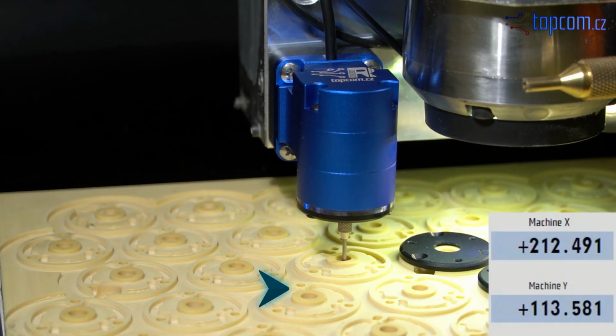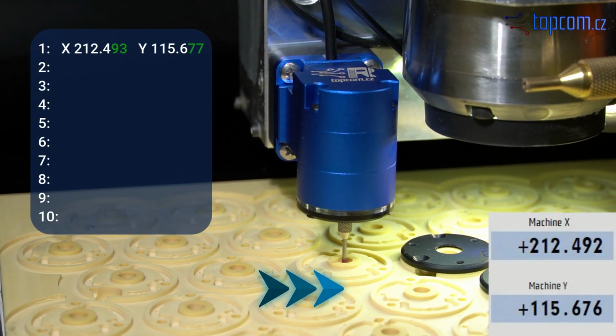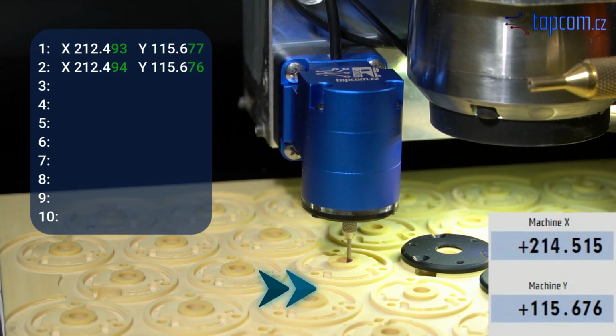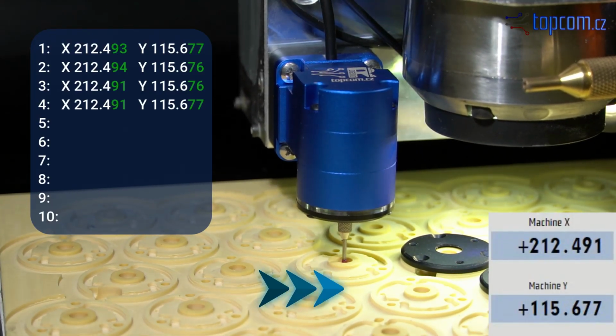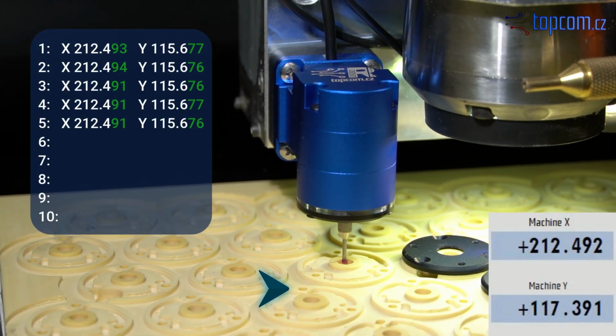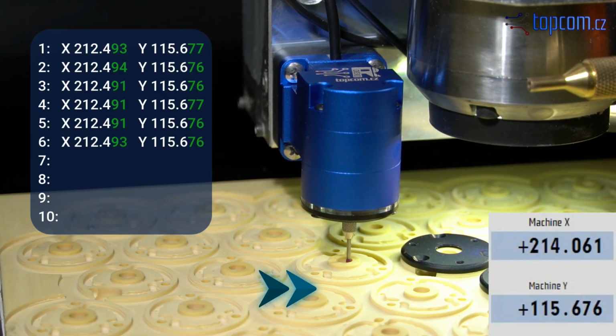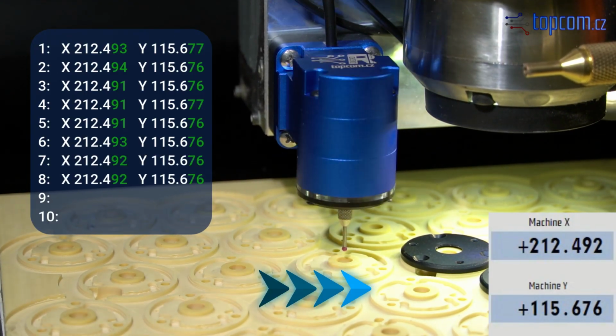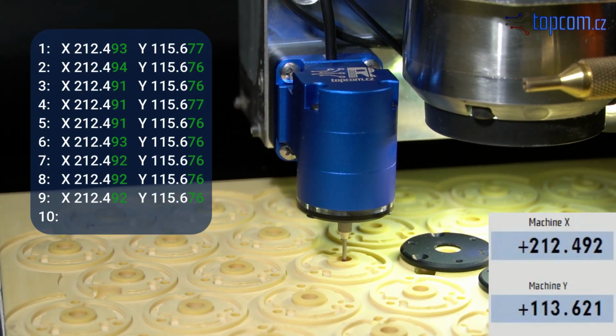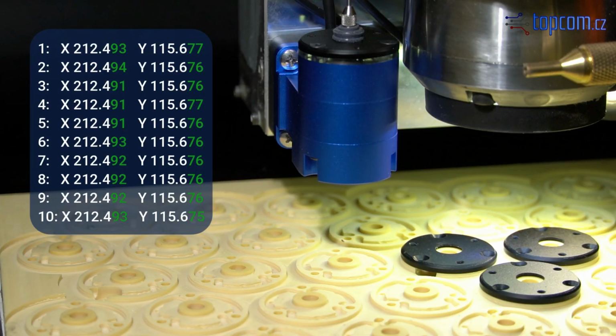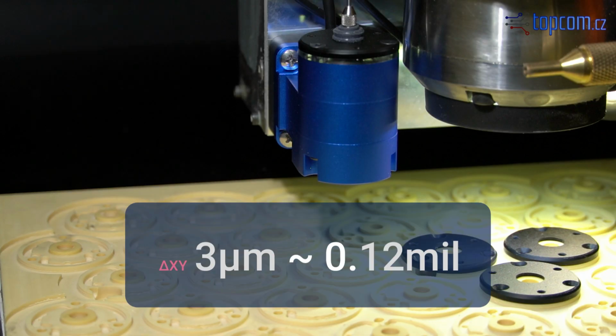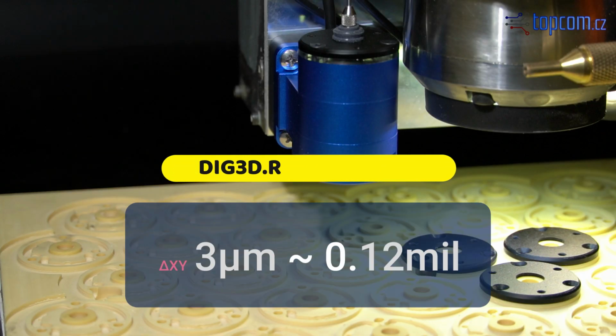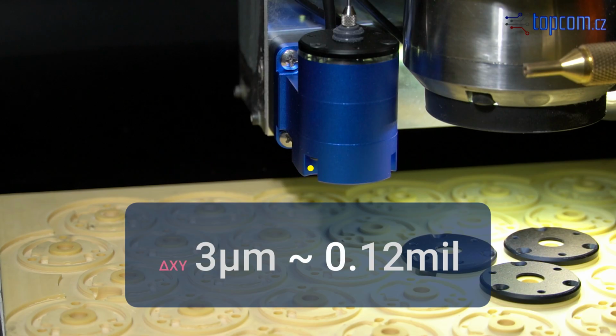We covered the repeatability testing of the DIG3D rotary probe in more detail in one of the previous videos. A major advantage of this probe handling method is the quick and potentially automated preparation, along with simple control. The resulting measured deviation of 3 micrometers, or 0.12 mils, is the best among all the tests performed. Even in repeated tests, the deviation never exceeded 6 micrometers.